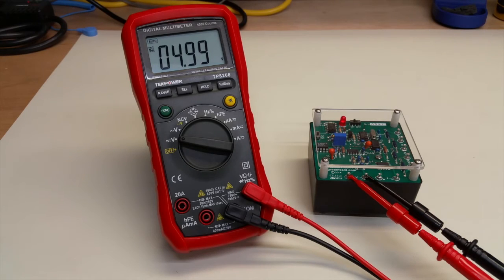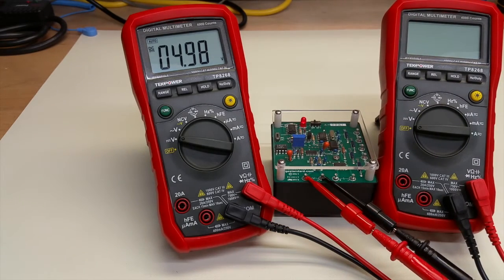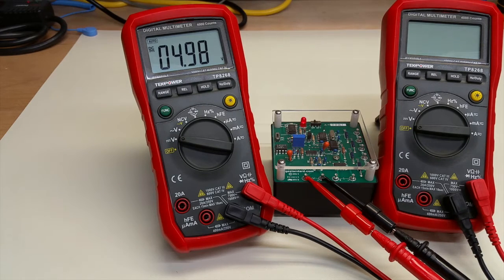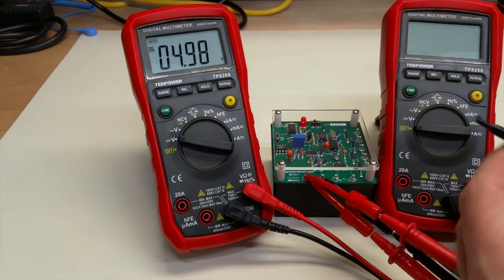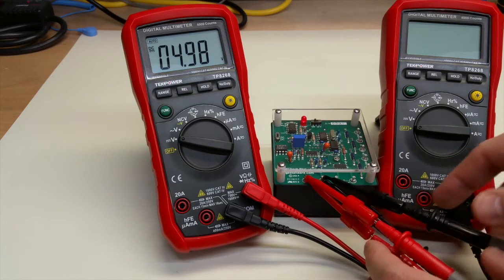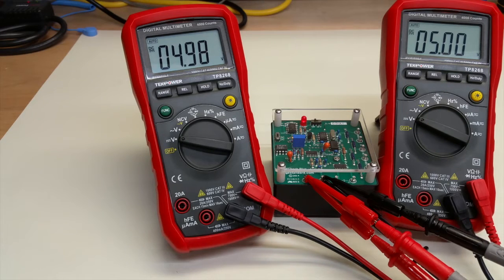I think it's also instructive just to see how these agree, to look at how two meters fresh out of the box agree. So I'm going to do that with the second meter. I'm just going to put the clips on here and attach those to the voltage standard as well. And I'm going to turn this on and you see that this one actually does read 5.00 or 5.01, a little bit of fluctuation going on there. So both of these meters are certainly agree to within specifications and interestingly the meter on the left is changing just a little bit, but good show for the accuracy and the consistency of the DC voltage.